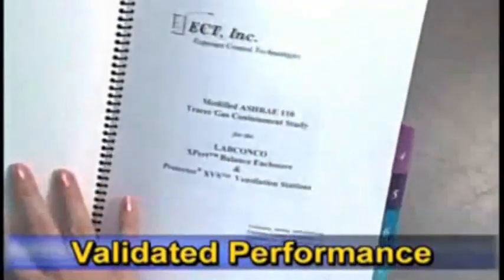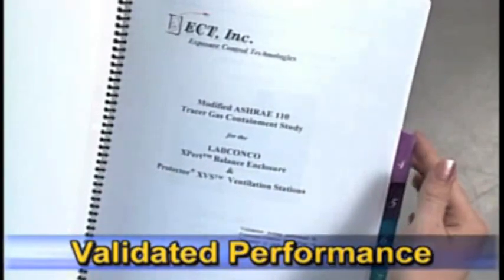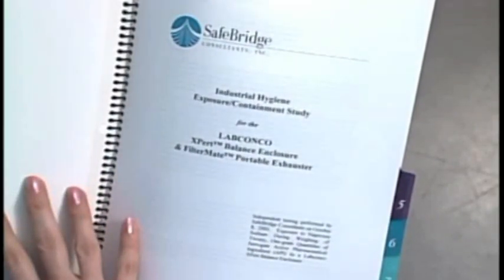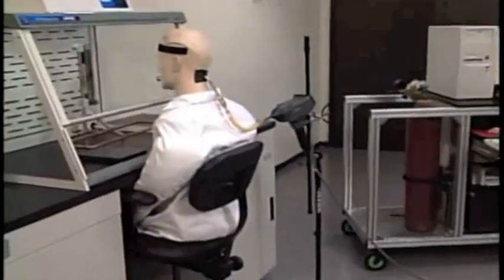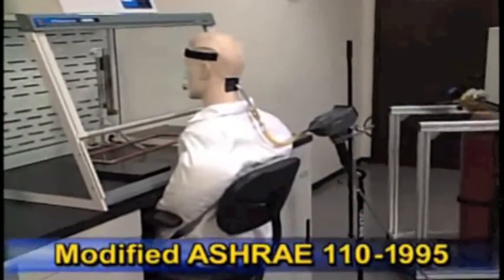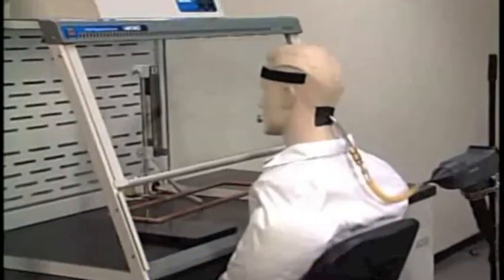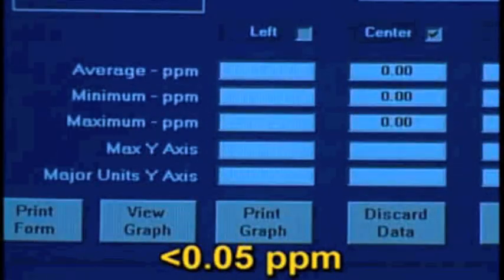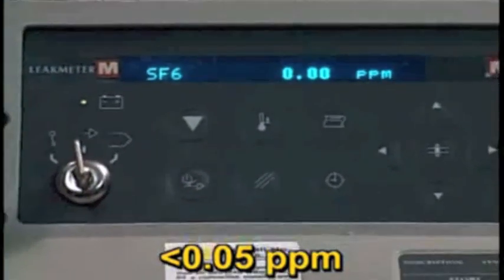Independent testing conducted by ECT Incorporated and SafeBridge Consultants confirms that the XPert Balance Enclosure provides containment of both gaseous and particulate contaminants when operated at face velocities of 60 feet per minute. ECT Incorporated conducted ASHRAE 110 1995 testing and found that average concentrations during tracer gas tests were less than 0.05 parts per million, and no escape was observed during the smoke tests.